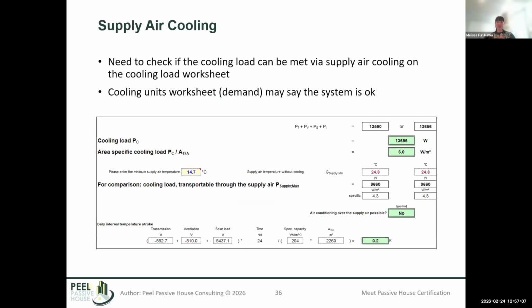If you're doing supply air cooling, cooling through the ventilation air, on the cooling load worksheet there's a check where you can input the minimum supply air temperature, the lowest temperature of your supply air. It'll then check whether it's possible to cool just through the ventilation air. On the cooling units worksheet it may say the system is okay, but you really have to check that you have enough air to meet the load on the hottest day.